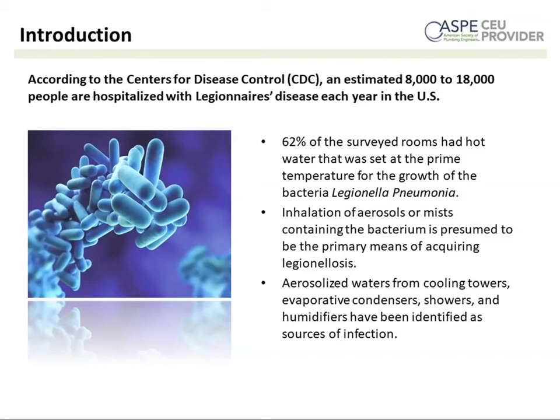Now, on the other side of the coin, in terms of Legionella, the Centers for Disease Control estimates that 8,000 to 18,000 people are hospitalized with Legionnaires' disease each year. And you've got to remember too, in 62% of the hotel rooms that we surveyed, the hot water was at 115 degrees or below. So the ideal temperature range for Legionella is between 95 and 115.